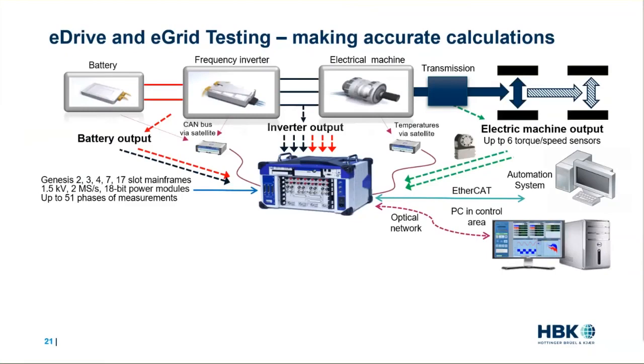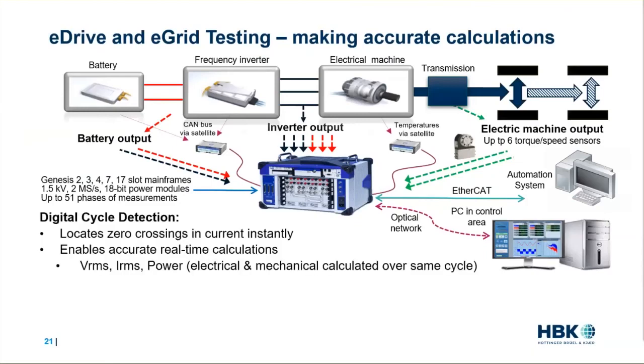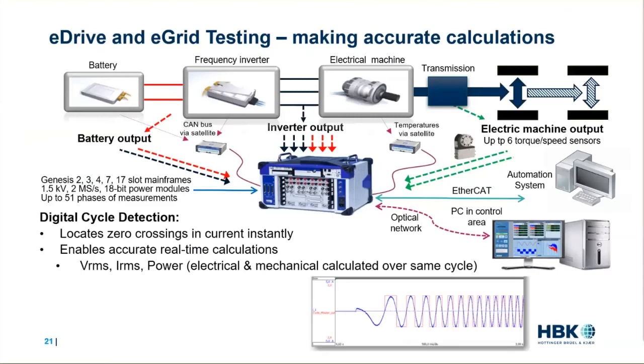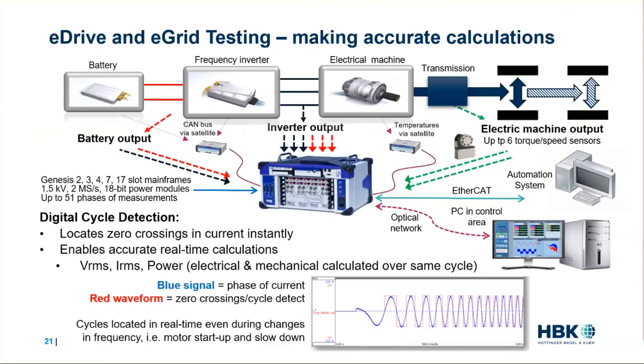Well, all calculations across the entire drivetrain must be done on an integer number of cycles in order to produce accurate results, such as true RMS measurements. Digital cycle detection locates zero crossings instantly, which enables accurate and real-time results even during speed changes. For example, in the diagram at the bottom, the blue signal is one phase of current increasing in frequency. The red waveform shows the detected zero crossings on the current for every cycle, and the red waveform is then used as a cycle master to accurately calculate for every full or half cycle, you decide, the true RMS voltage or current, or even calculate the electrical power over the same cycle as the mechanical power.